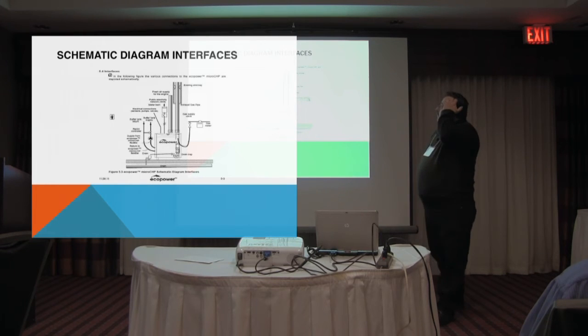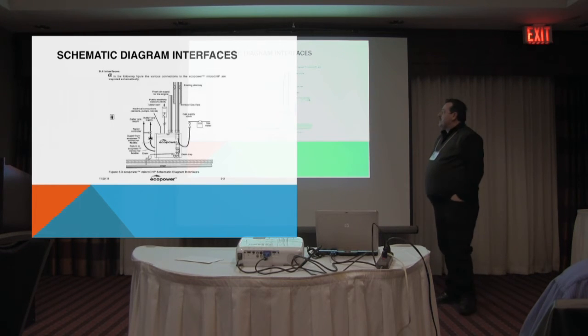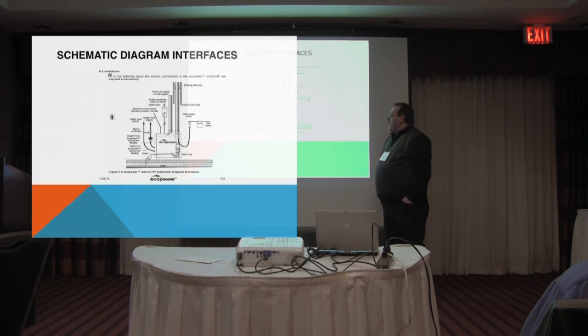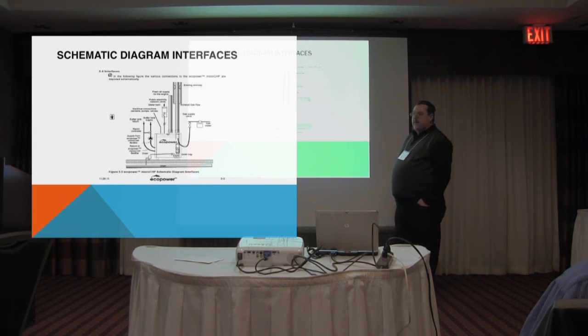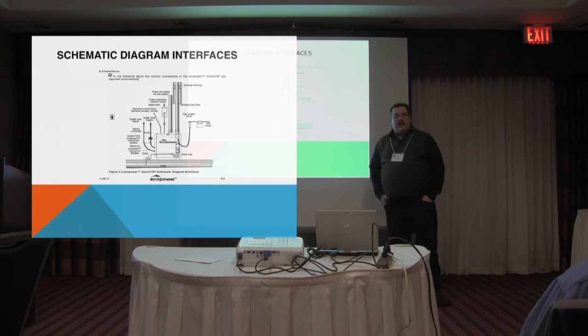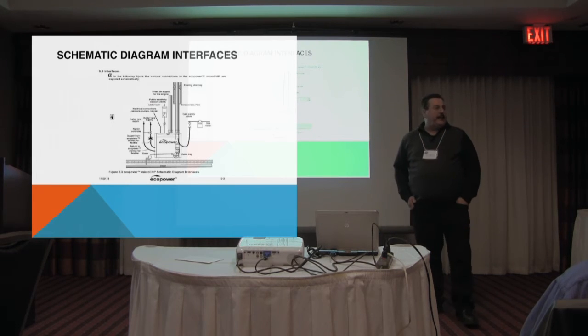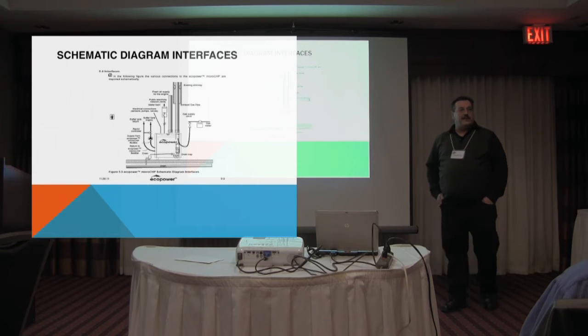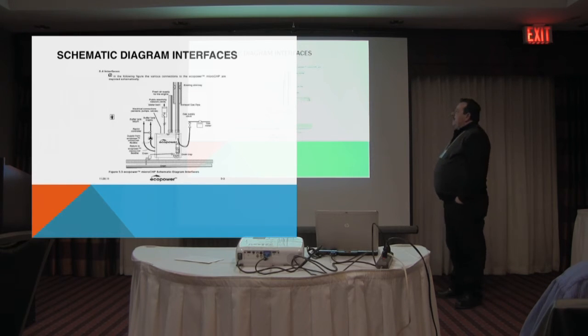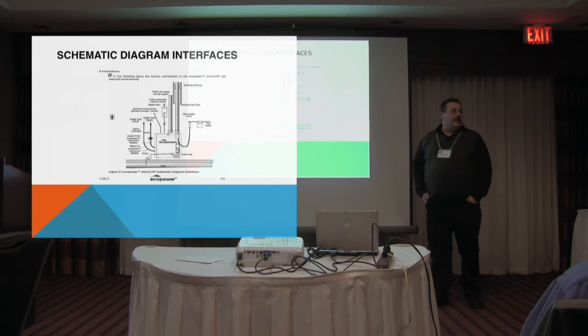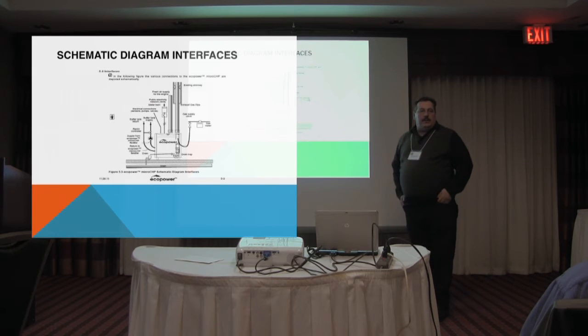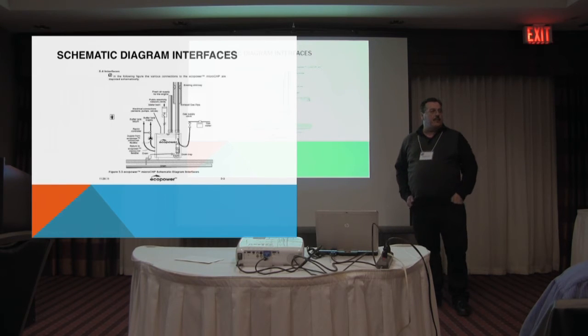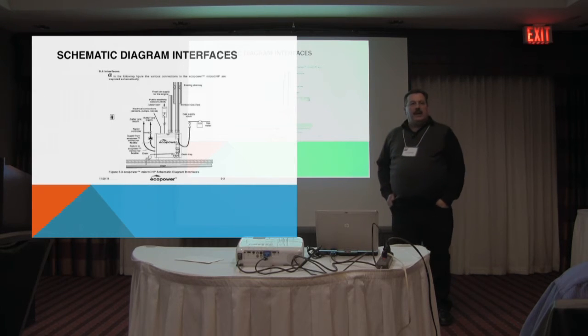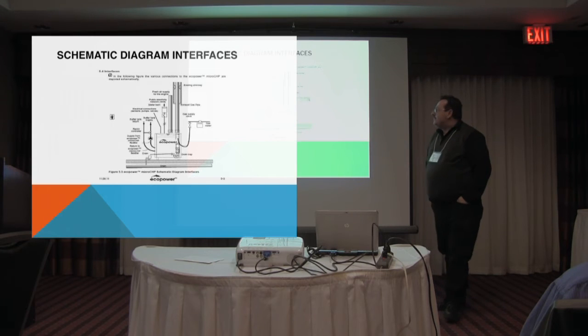As far as interfaces go on these systems, really what we have is an appliance. We're going to have to do some venting on it. These are actually condensing units, so they can condense. You're running an internal combustion engine that condenses, or can condense. And so the vent pipe typically is going to be CPVC, or sorry, there are a couple of brands of polypropylene pipe, Polypro, or any of the other brands that are out there.